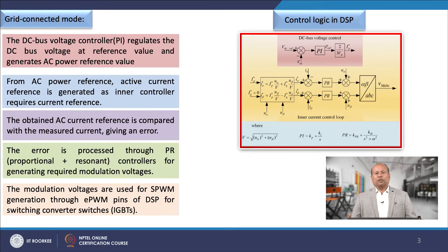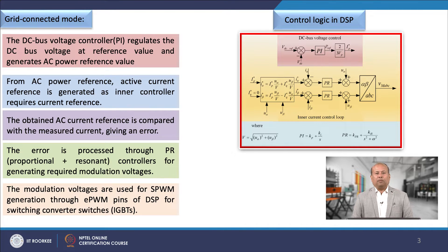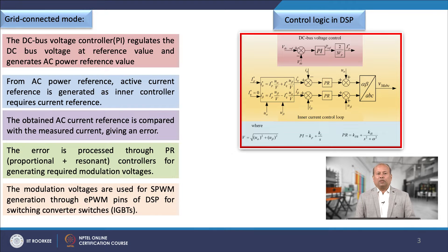Now, the grid-connected mode of operation: this slide shows the control logic used for interfacing the DC microgrid with the AC grid. The DC bus voltage controller regulates the DC bus voltage at the reference value and generates the AC power reference value. The active current reference is generated from the AC power reference, as the inner controller requires a current reference. The obtained AC current reference is converted to the stationary reference frame, and this current reference is compared with the measured current, which normally gives an error.